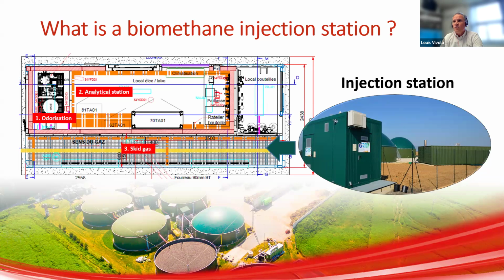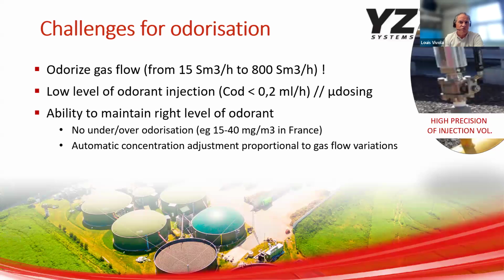So here you can have an overview of an injection station. You can see these three parts: the odorization area, the analytical station, where inside we also have the PLC automation system to control the installation, and the skid gas. What is important to consider is the fact that in odorization, we work in a hazardous area, so it's a classified area, and so we need to have ATEX or CSA certified equipment. Next slide, please.